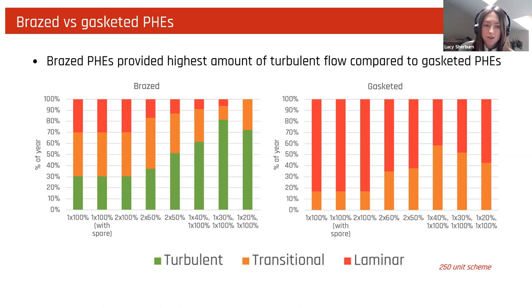So just going back to the theory a little bit, your ability to transfer heat effectively depends on the turbulence of the medium. So high turbulence is really desirable. Laminar flow, which is at the opposite end, where you have low flow rates through your plate heat exchanger, gives poor performance. Your velocities are reduced. This can result in scaling and fouling on your plate heat exchanger. It can also increase the pressure drop across your unit. So this has a knock-on effect in terms of maintenance, lifespan, and your ability to transfer heat effectively.